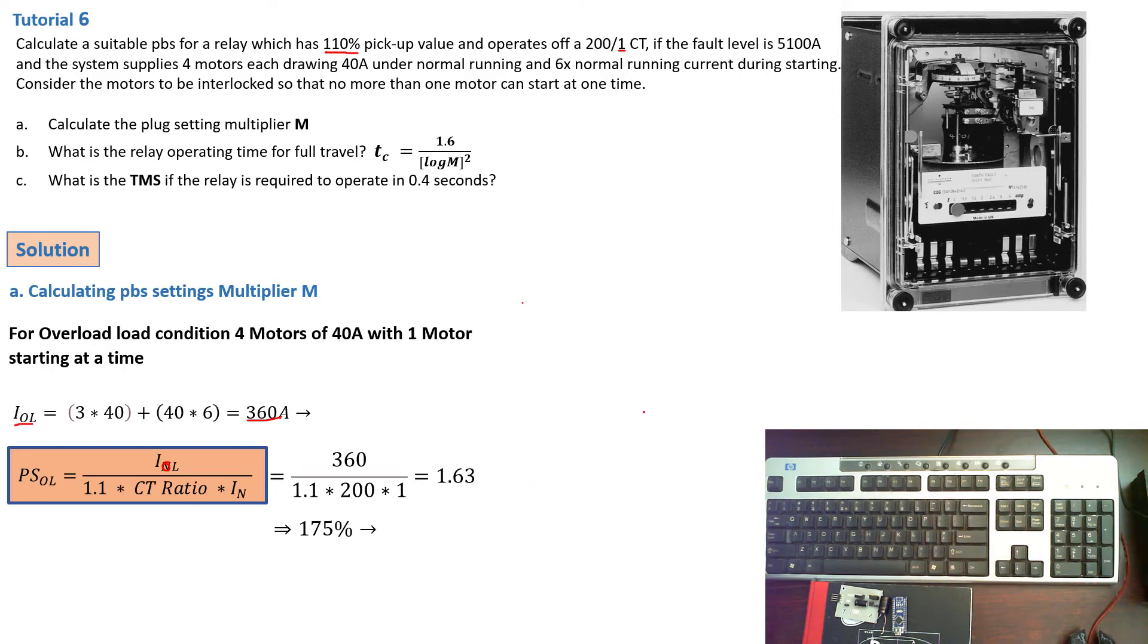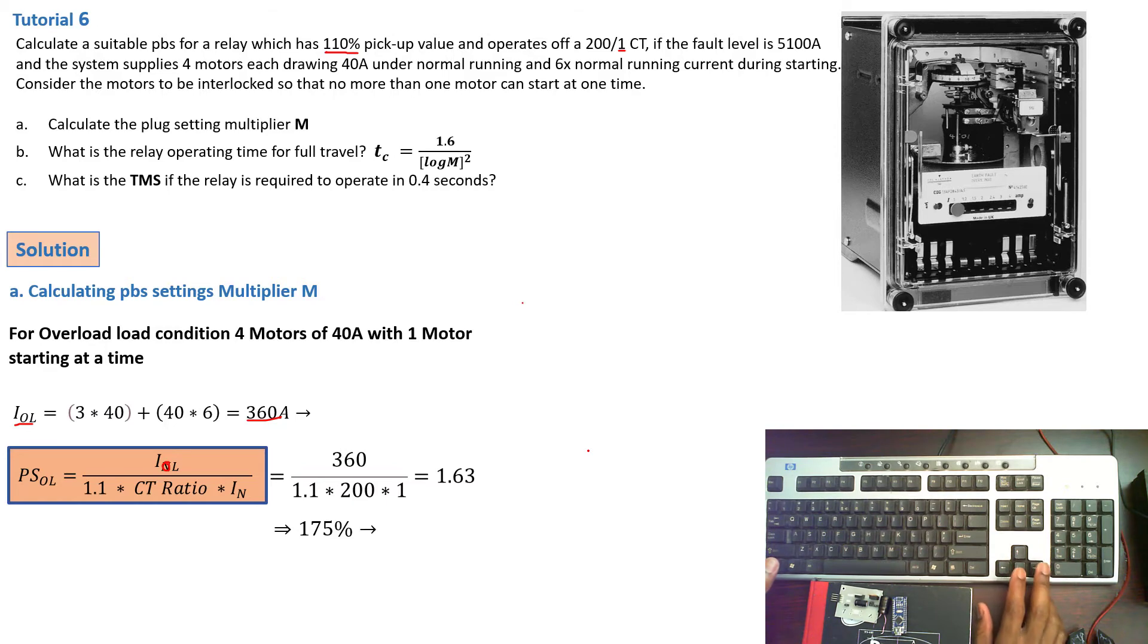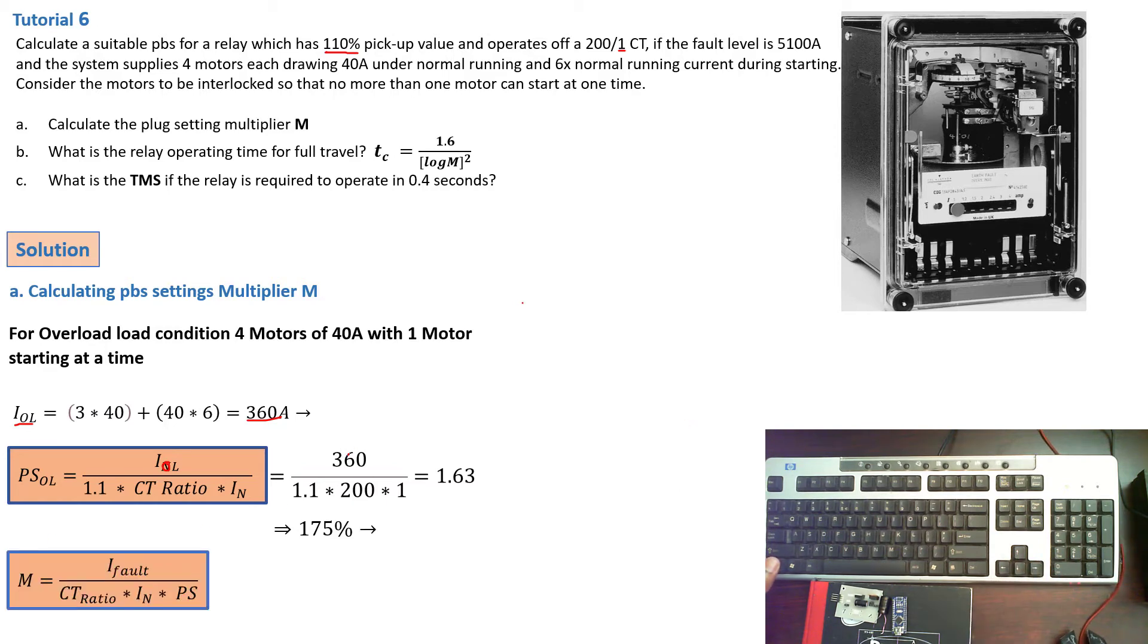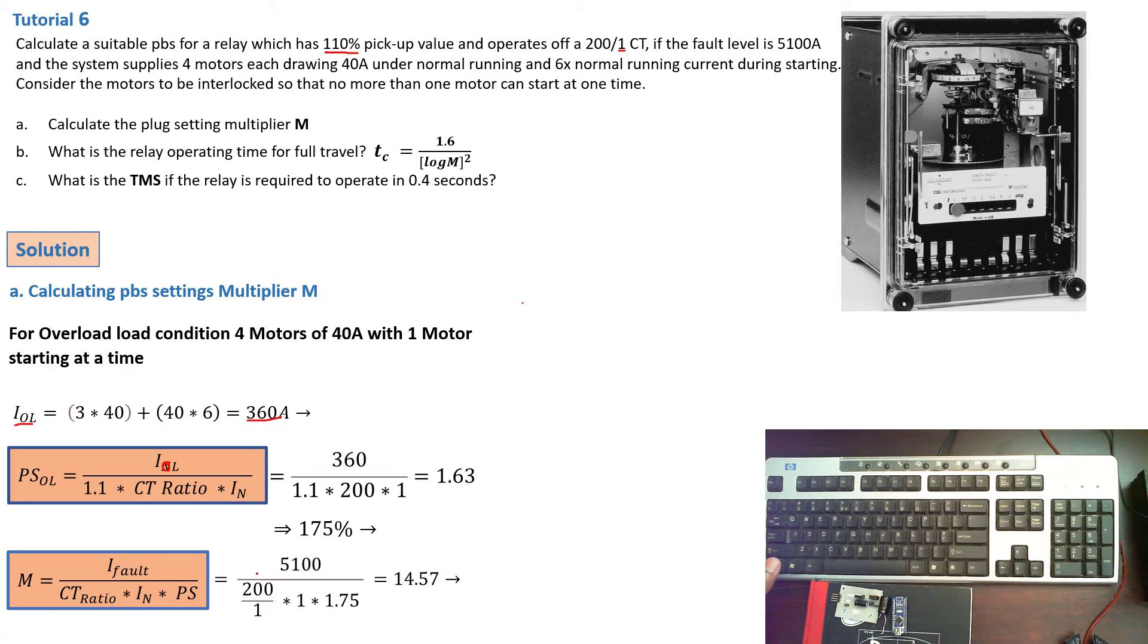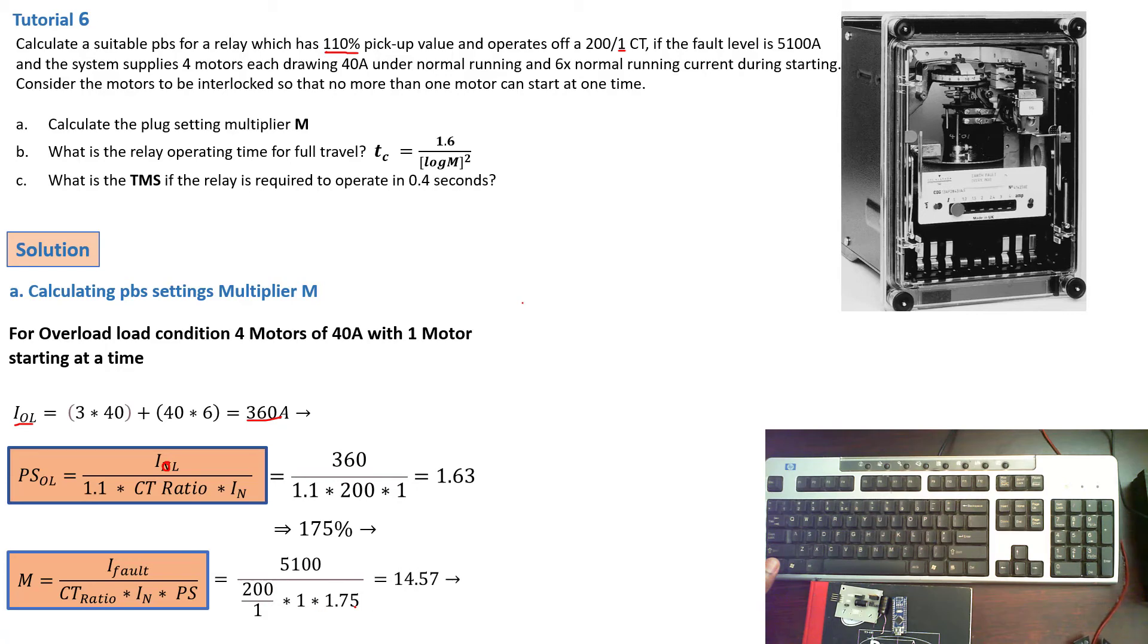175%. Now moving on, we can then calculate M using the M formula that is given by M is equal to I-fault over CT ratio times IN times the plug setting. We already have the plug settings and the fault current. We can then go ahead and replace. So that will be 5.1 kilo amps over the CT ratio times 1 and our plug settings that give us the M value of 14.57.